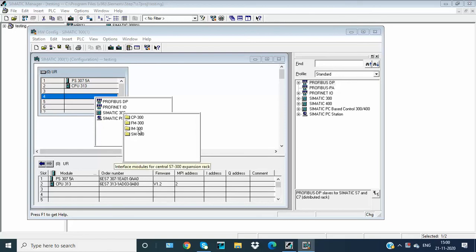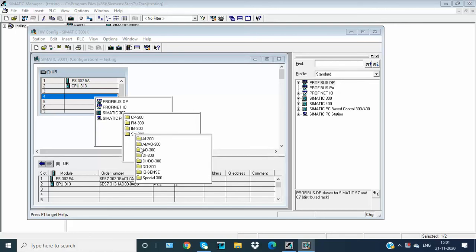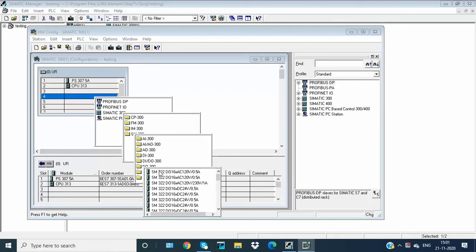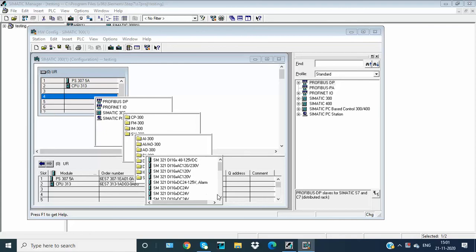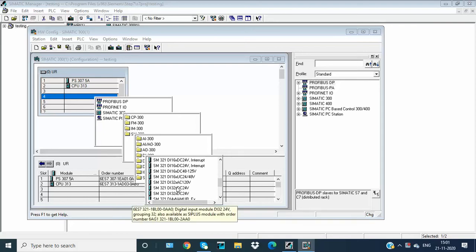On the third position I am leaving it blank because I am not using any interface module. Now I am using SM300 on the fourth position — SM300 digital output. I am using 322 with 32 outputs. For digital inputs I am using SM321 with 32 inputs at DC 24 volt.